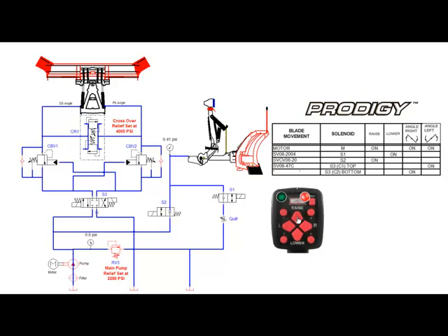Pressing the raise function will engage both the motor relay and the S2 coil. S2 valve will shift allowing fluid to flow to the lift ram. Once the lift ram is fully extended, fluid will flow through RV3 and back to tank. RV3 is our main pump relief which is set to 2250 psi.